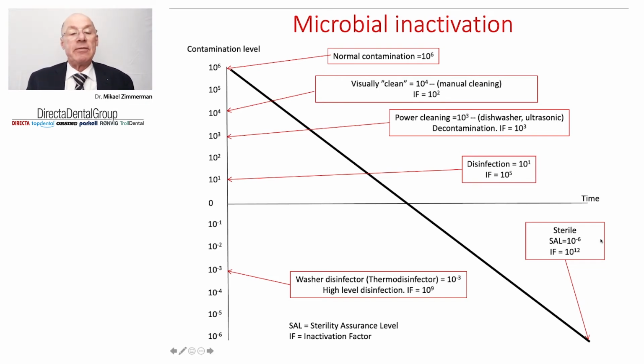different inactivation factors. The washer disinfector, the thermal disinfector, actually has a theoretical inactivation factor where you come down below zero, theoretically calculated below zero. And when we talk about the so-called sterility assurance level, which I mentioned in the last slide, we can measure the reduction of microorganisms down to zero.